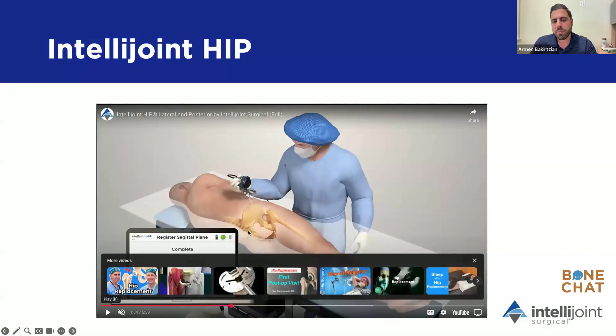So the way we do registration is, perfect timing actually, that's where we are in the video. We benefit from the proper positioning of the patient on the OR table. Just like any surgery, the orthopedic surgeon and the support staff want to properly position the patient. They want to make sure that the ASIS points are stacked on top of each other, and that the patient's not rolled in any direction. So with the patient in that position, before we make any skin cuts, our system is able to register the horizontal plane or the sagittal plane of the body. That's the step that's happening right now. And the surgeon does that with a simple click of the button. They hit the green button on the camera and the system registers the sagittal plane.